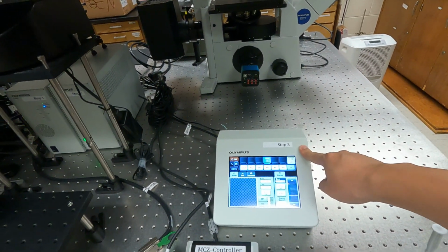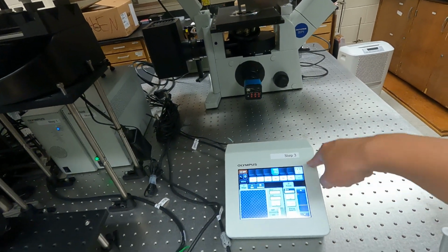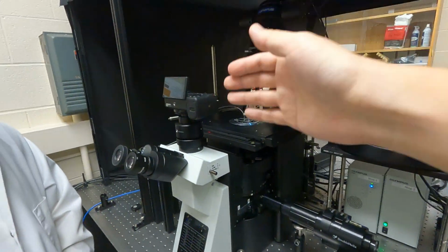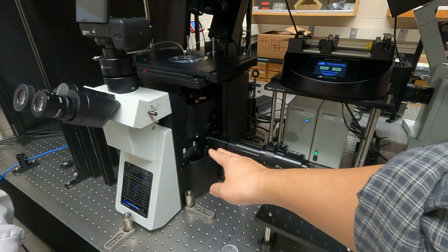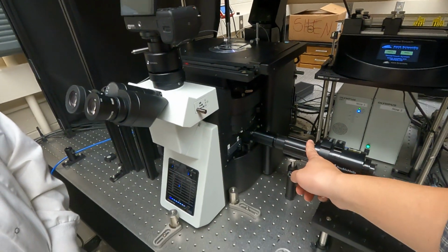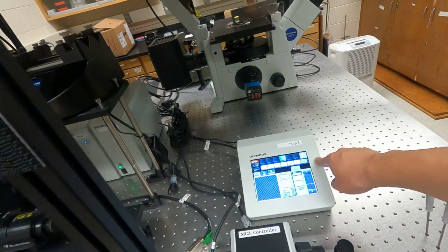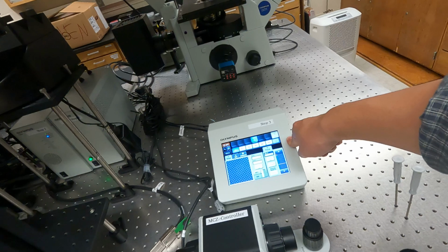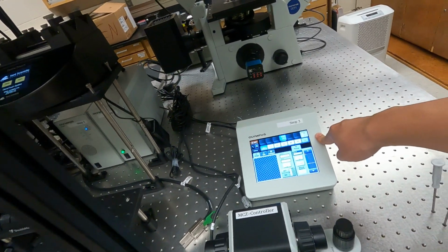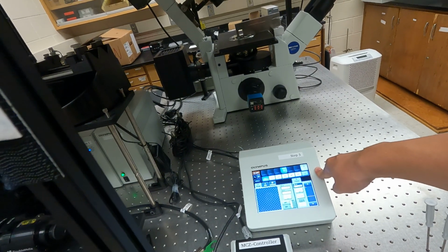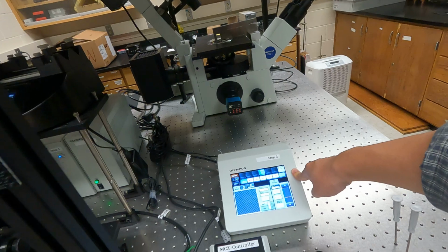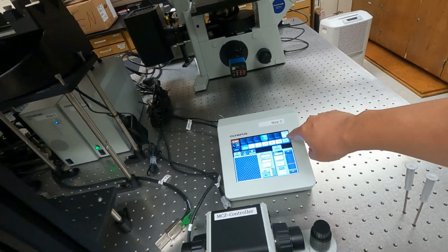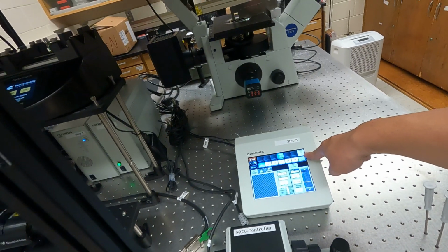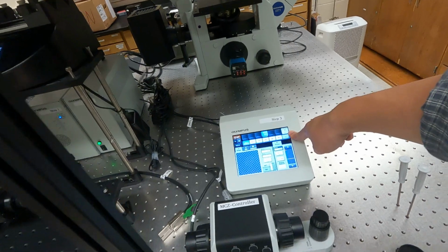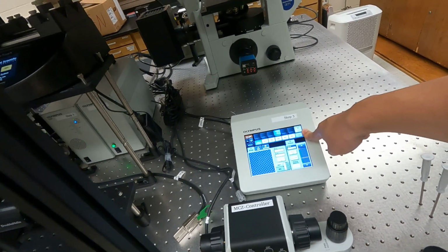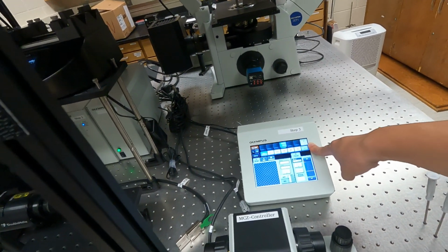Pressing it twice, you see both the eye and the camera. So this is a 50-50 splitting of the light: 50% of the light goes into the eyepiece, and the other 50% goes into this camera. If you press it a third time, it will go back to the camera mode, meaning all of the light will get into the camera. For our single molecule experiment, the amount of photons generated from the catalyst will be very few. So by default, we should select this camera mode and let 100% of the photons go into the camera. Unless we're doing some other type of detection, we will not select the eyepiece or the 50-50 splitting.